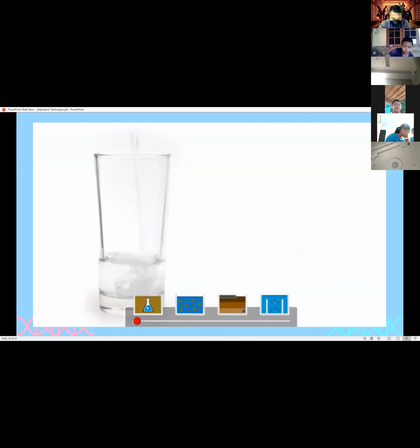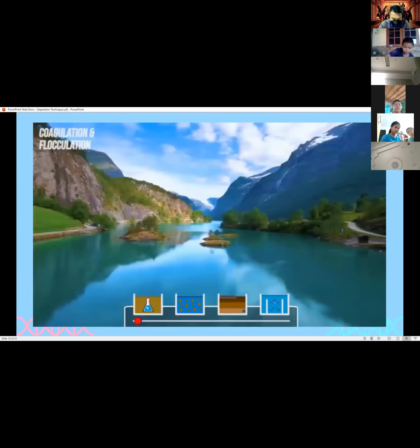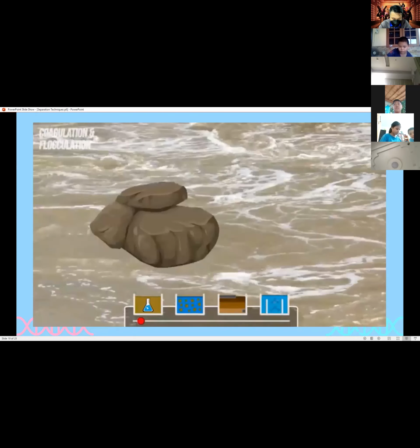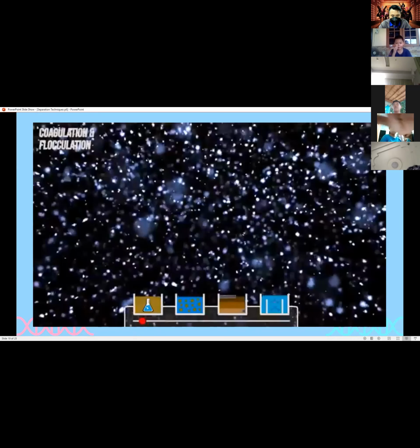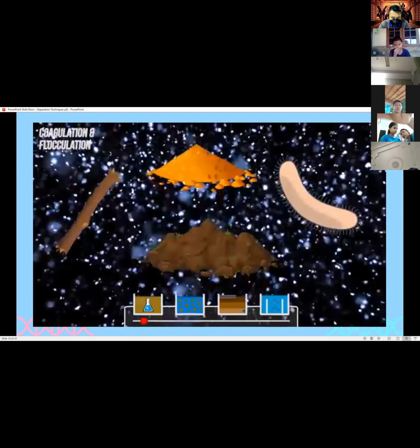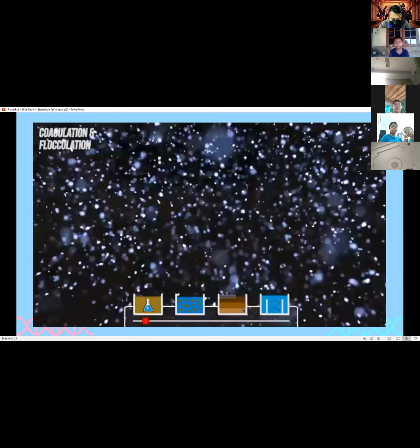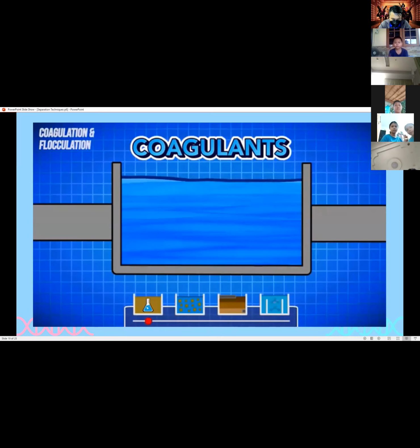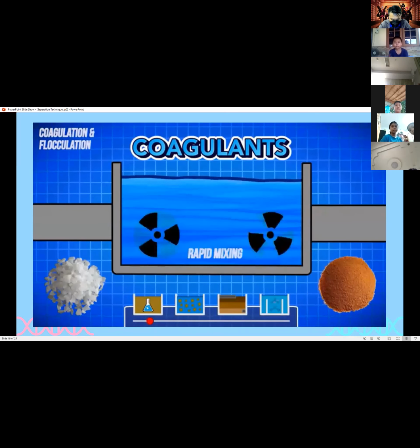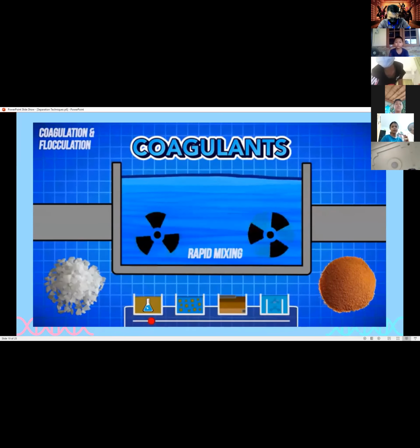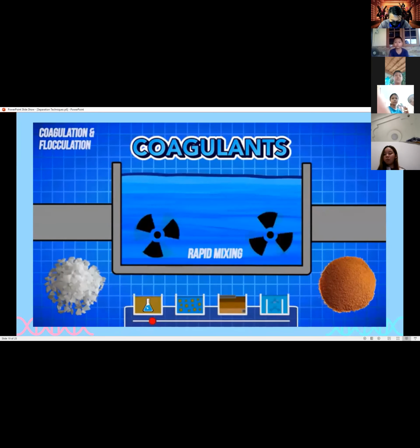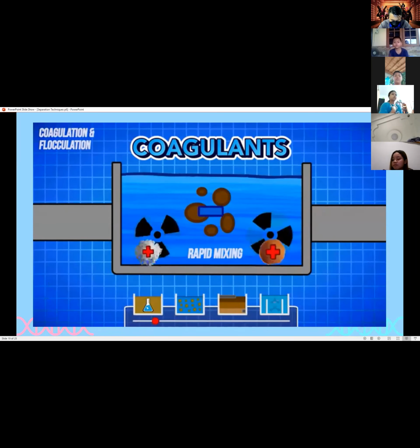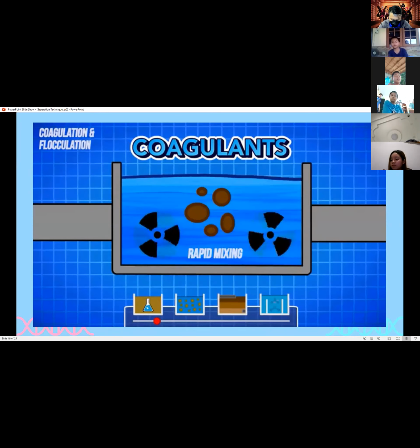All drinking water has to come from somewhere, usually freshwater lakes, rivers, wells, or streams. In these water sources, there's going to be some amount of sediment as well as organic materials in the water. These particles of sand, bacteria, dirt, wood, etc., all have to be removed before the water can be sent out to city residents. To do this, chemicals called coagulants are added to the water. These chemicals, such as aluminum sulfate or ferric chloride, work to help the particles in the water congeal together. Essentially, these chemicals have the opposite charges of suspended solids, like clays or silts. When combined, the charges of the particles are neutralized, allowing them to stick together.